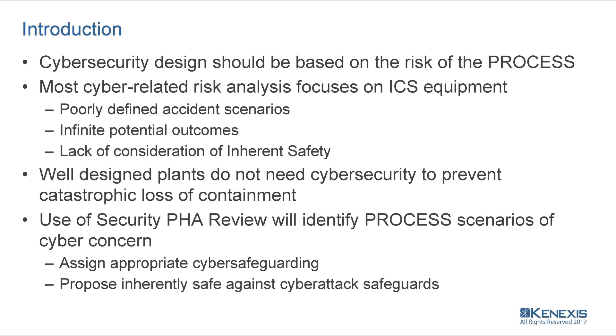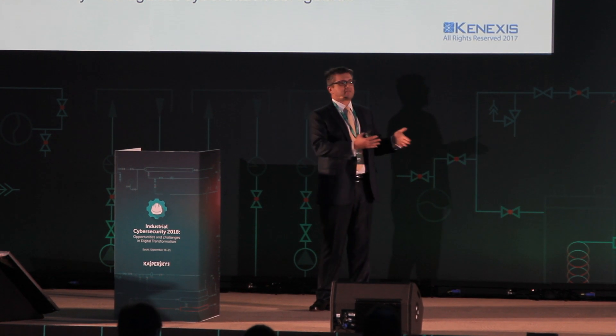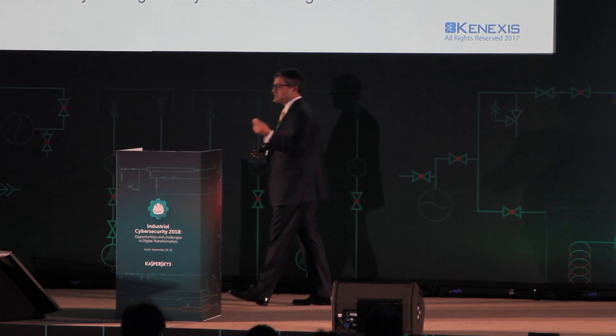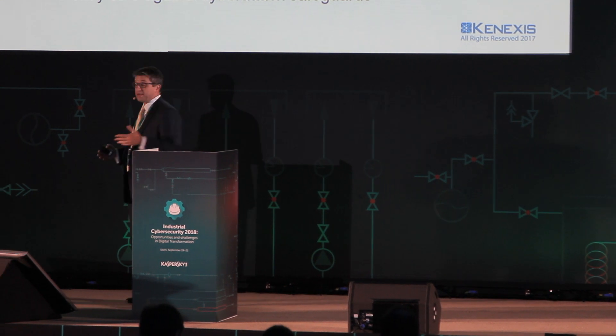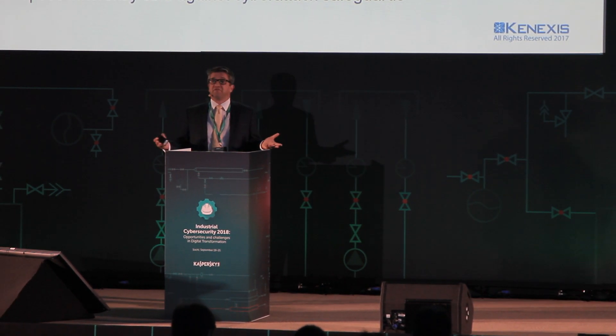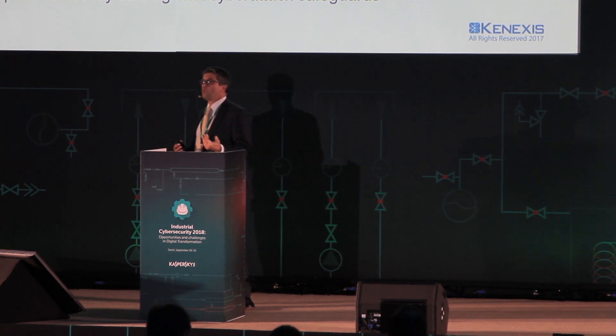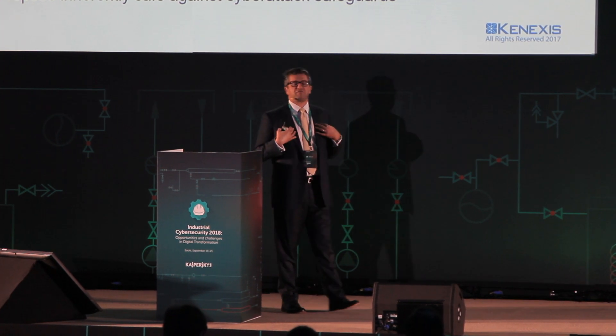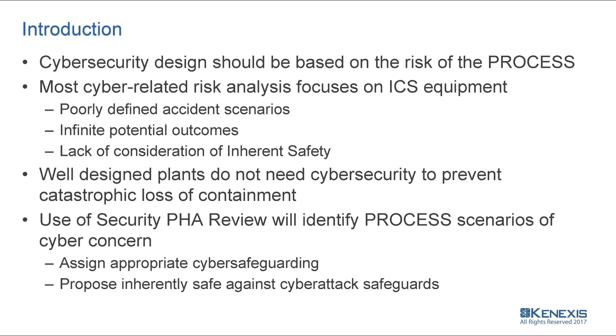So you end up with poorly defined accident scenarios. You simply know that someone can take remote control of the process, but what are they going to do with it? That's the important part that's not discussed. That also results in infinite potential outcomes on what someone can do when they get control of your plant. From a process safety perspective, that approach ignores the most important way to make your processes safe, which is through inherent safety — making sure that the plant is designed in such a way that it can't fail.